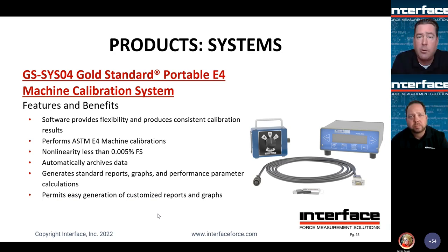So E4 calibration systems, typically speaking, will consist of a 9840, an ethernet cable, and the CX box, and the software set. Obviously, normally we'd have a load cell also associated with this set at some point in time. That's going to be dependent on the force range and what form factor requirements each application has. The CX box is used as a check device for the 9840. The 9840 is not actually used for display purposes in this particular setup.